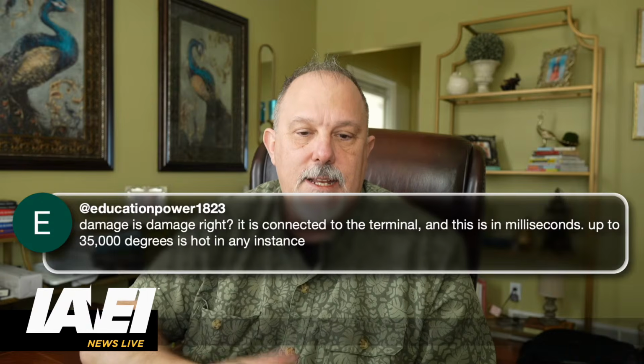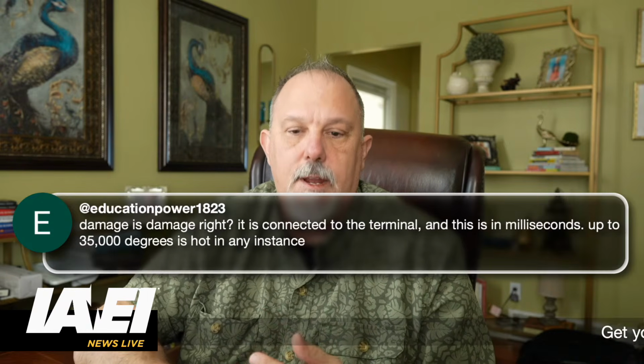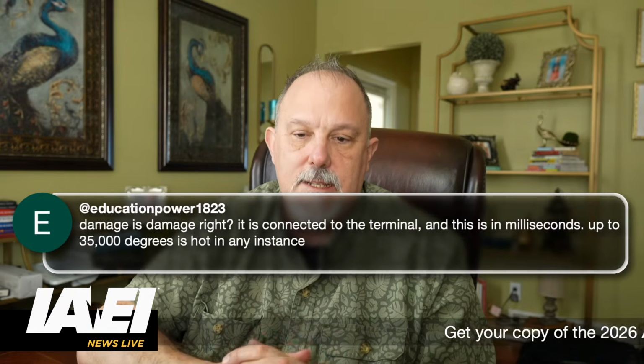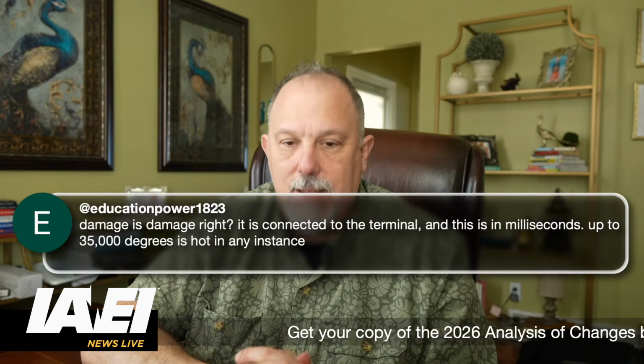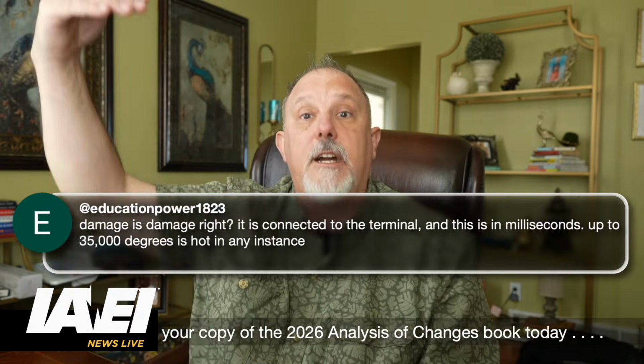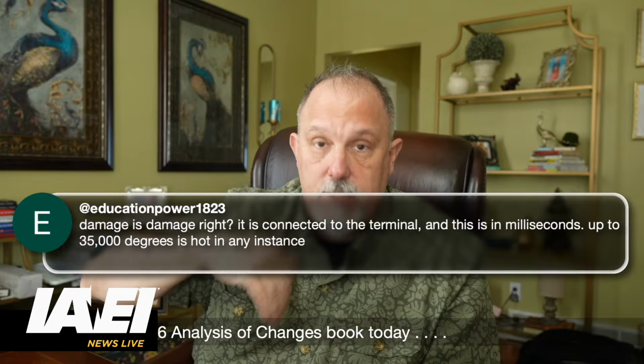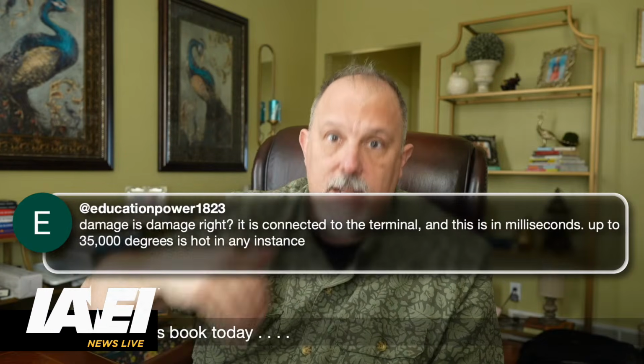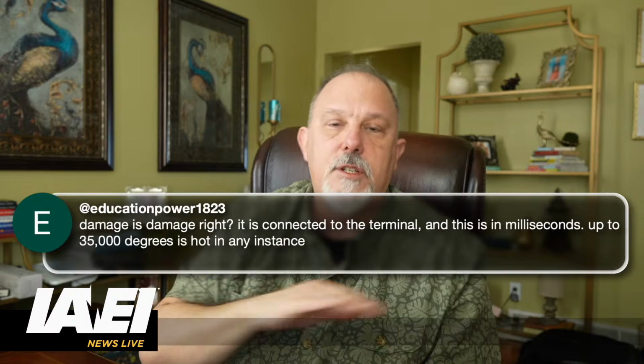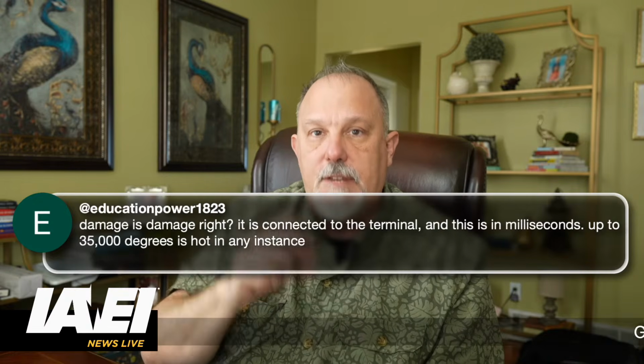Damage is damage, right? It's connected to the terminal, and this is the milliseconds up to the 35. Now, if you're dealing with conductors going into equipment that's had the arc flash event, absolutely, you have damaged conductors.